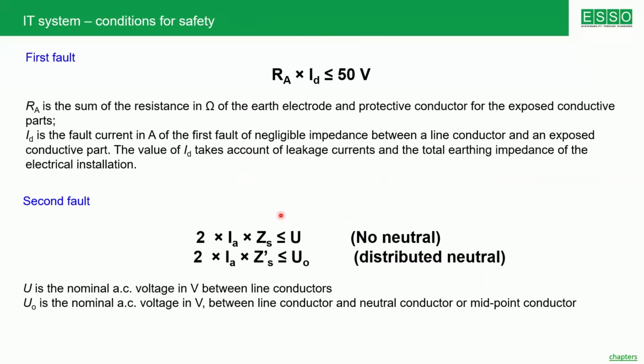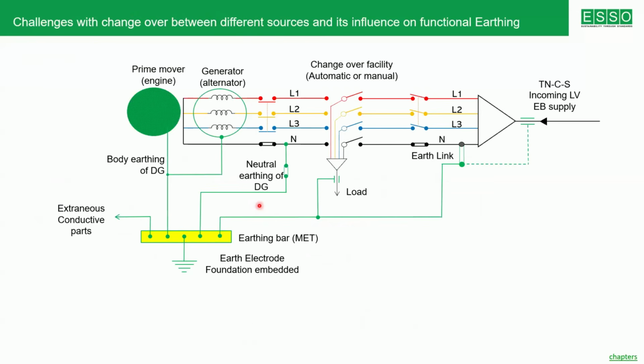Similarly, the calculations for IT system during the first fault as well as during the second fault, these are very well documented in the installation standard. Installation standard, please note, there is an equipment standard, there is an installation standard. Equipment standard means the biomedical equipment, because those are the equipment which you are finally going to use in a hospital. Probably there are other electrical equipment as well, such as lift, such as air conditioners, ventilators, and so on. Air conditioners, chillers, and so on, HVAC systems, so many other electrical items are there.